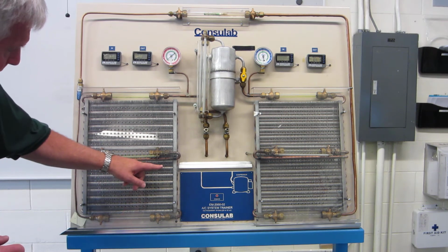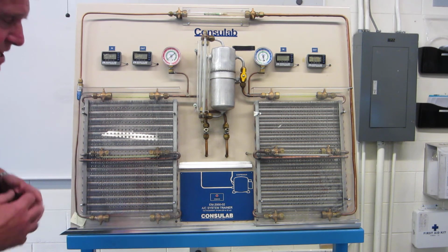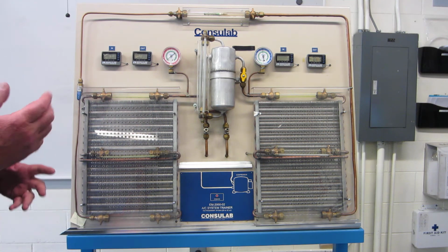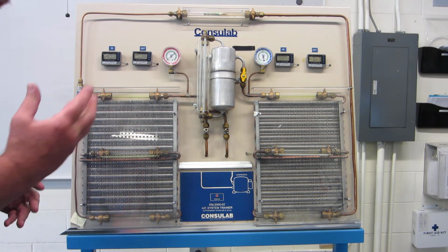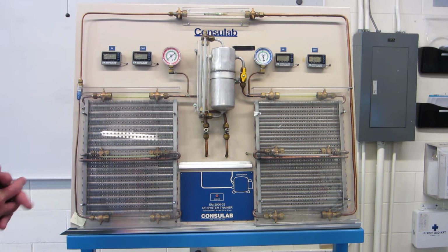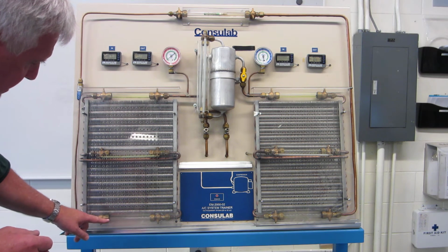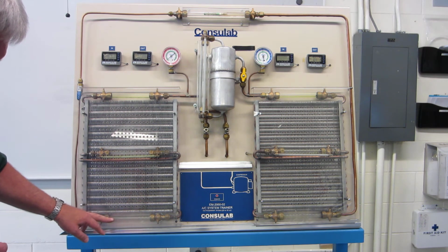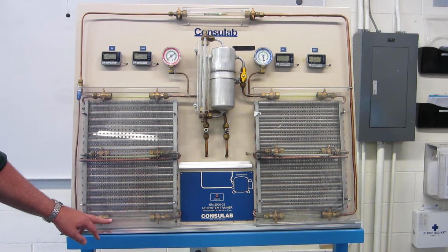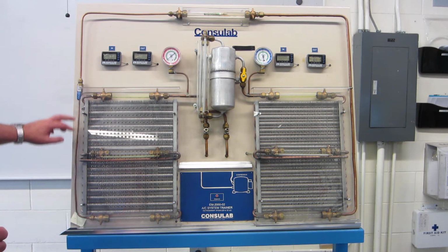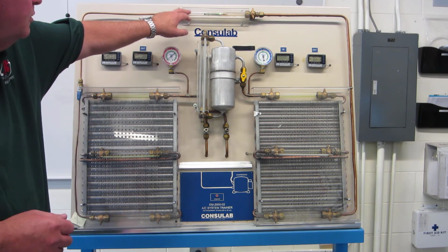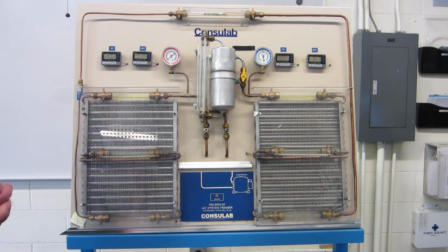And as it keeps going back and forth through the condenser and keeps giving up heat energy, we'll get what we call subcooling. We're able to give up heat energy. Subcooling is a change in temperature with no change in pressure, which means now coming out of the condenser, and you guys will be able to see on the bottom too if you have a look at this, we should now have a high temperature, high pressure liquid that continues off and onto the orifice tube.